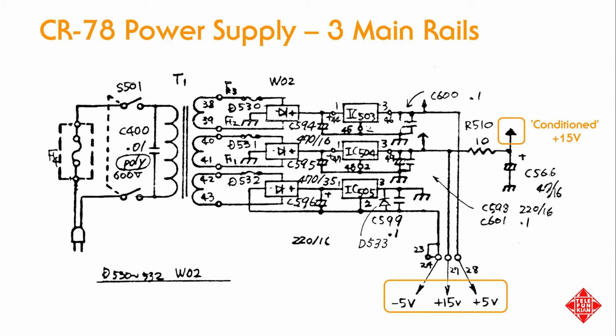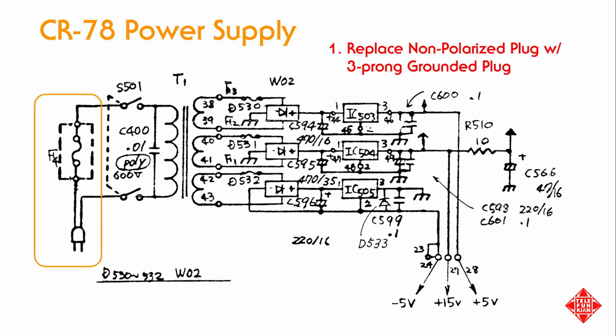In this video, we'll describe a number of changes we'll be making to ensure that this instrument continues to operate safely for years to come. The first thing we'll want to do is address the non-polarized power plug, which I believe has some potential to present as a safety hazard. My personal preference is to have all of the audio equipment in my studio properly grounded, so we'll be adding a 3-prong grounded plug that will also ensure that whenever the instrument is plugged in, the hot line will enter the fuse before it goes anywhere else in the instrument.